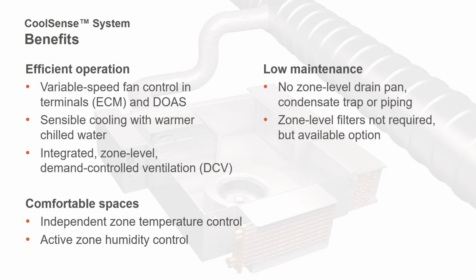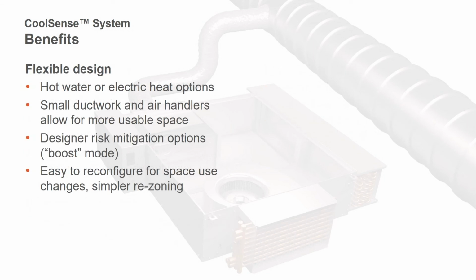Maintenance issues are minimized with no condensate system. And at the building owner's discretion, filters can be added to the terminal units to improve IAQ. The design offers flexibility with box orientation, options for electric or hot water heat, all while minimizing duct size and cost. And for the designer, they can build in flexibility for the future via boost mode with a system that's easy to reconfigure if the space changes.